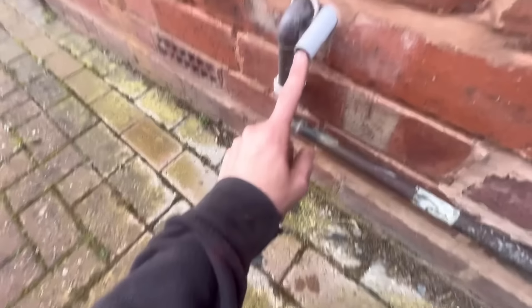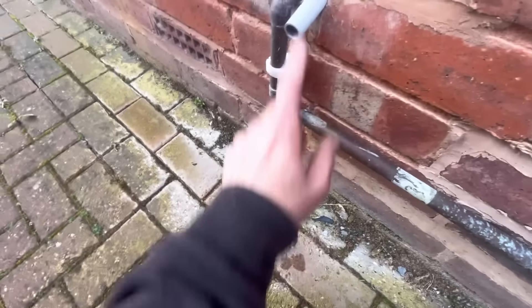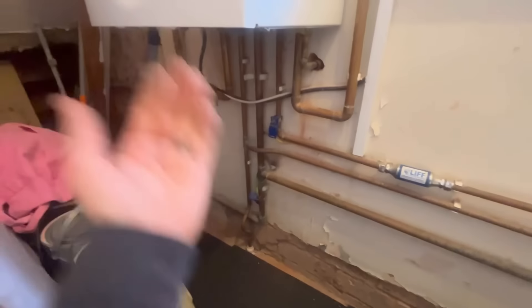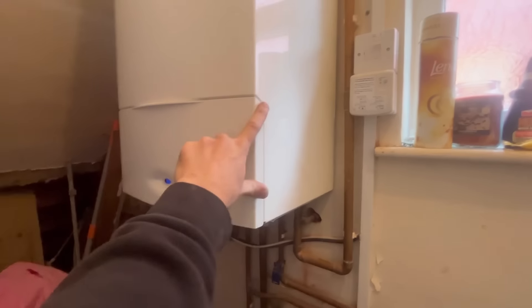That's not the safest in the world because that water will actually corrode the gas pipe — you can see it's already corroding the driveway. So we've got to put this right. What I'm thinking is: bring the pipe down here, across here, and into there. Put a boss onto here, a bit of pipe across, and back into the boiler. Then get that hole sealed up, sort that leak on the auto air vent, and then we can issue a safe certificate.